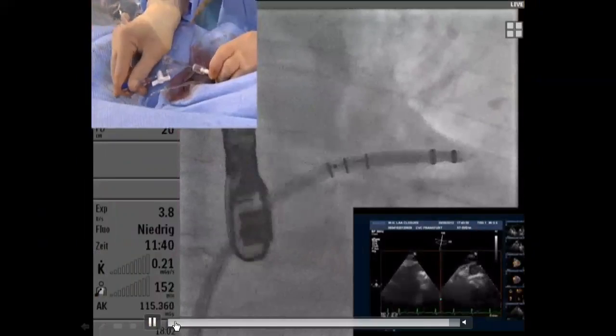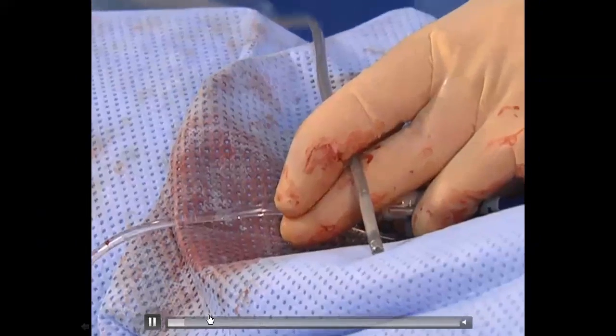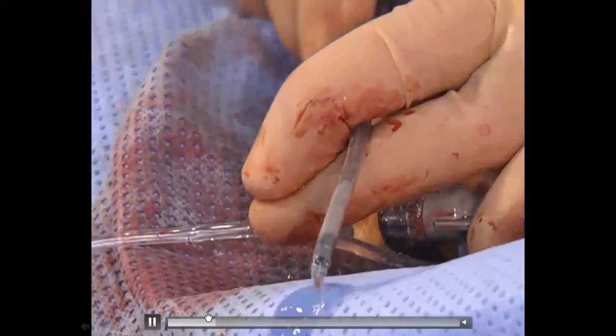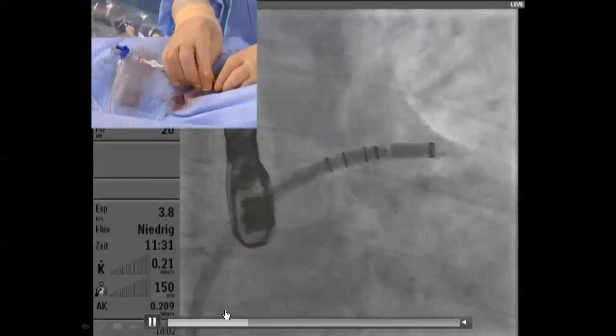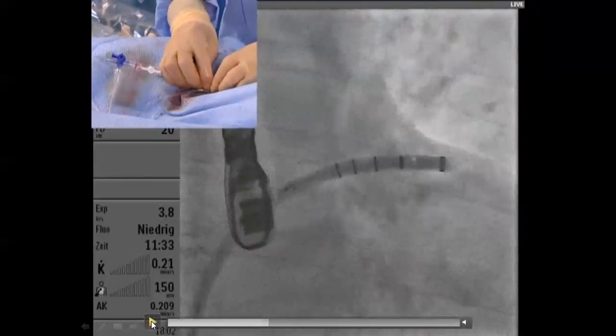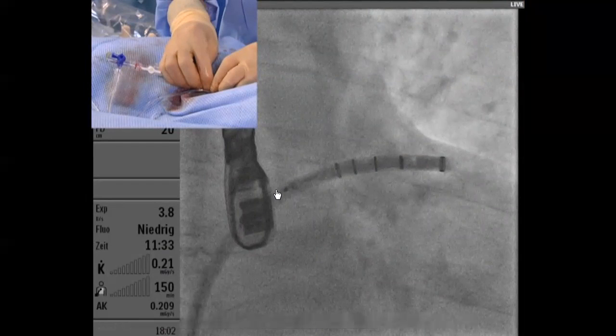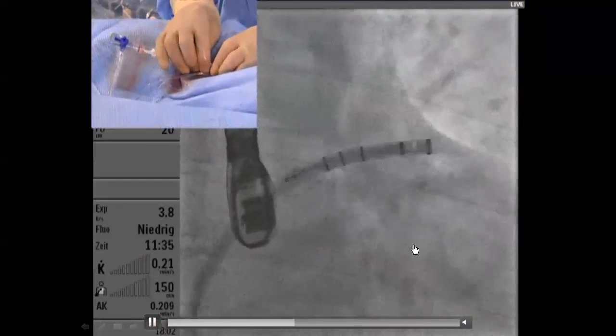And then you have to interlock the delivery catheter and the delivery sheath. The reason you do that is because the Watchman is attached to a cable. Eventually you'll hold the cable in place where you want it to unfold, and then you want to be able to take both the delivery sheath and catheter back as a unit. So you need to interconnect the delivery sheath and the catheter. There's kind of a locking mechanism when you do that.